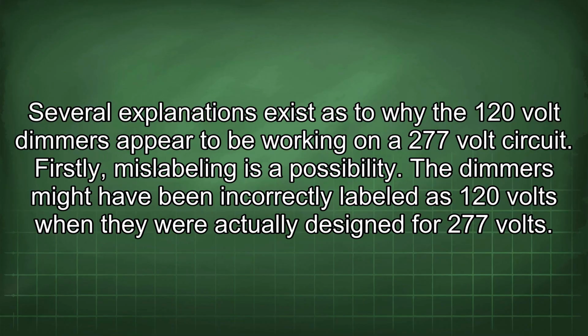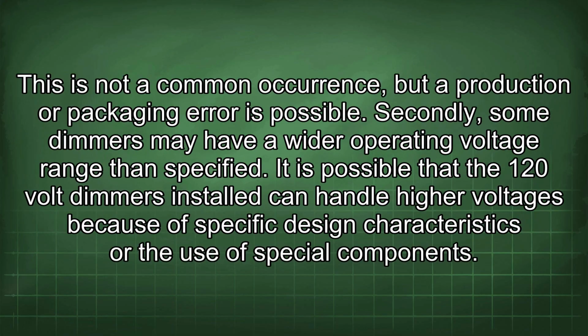Several explanations exist as to why the 120-volt dimmers appear to be working on a 277-volt circuit. Firstly, mislabeling is a possibility. The dimmers might have been labeled as 120 volts when they were actually designed for 277 volts. This is not a common occurrence, but a production or packaging error is possible.